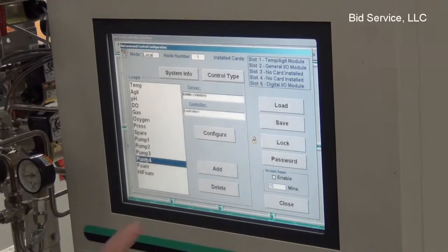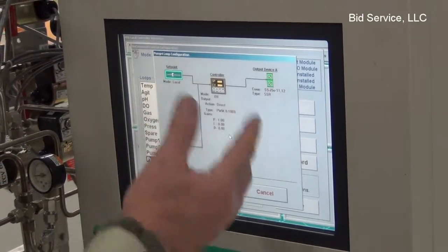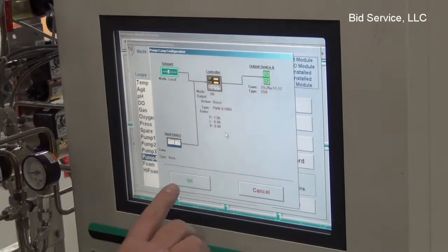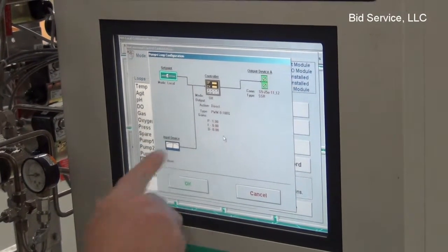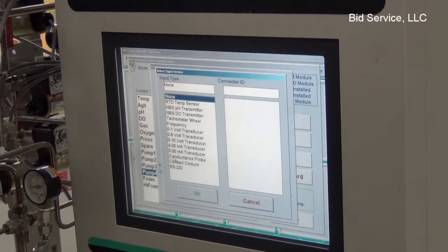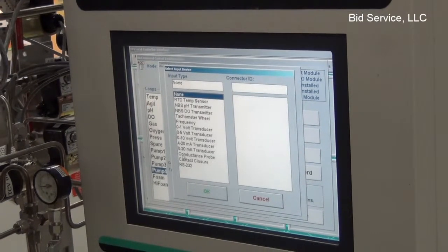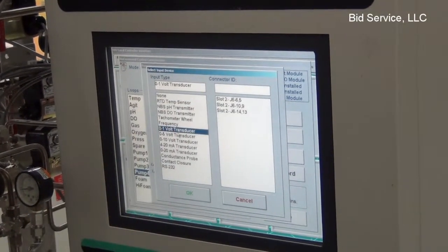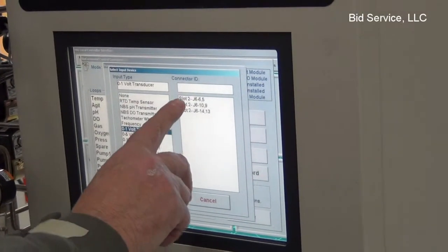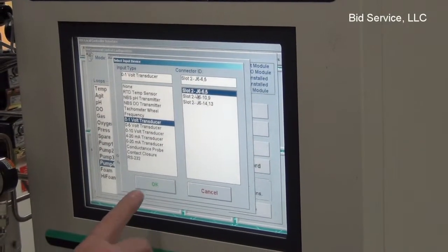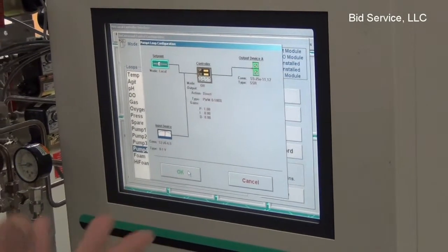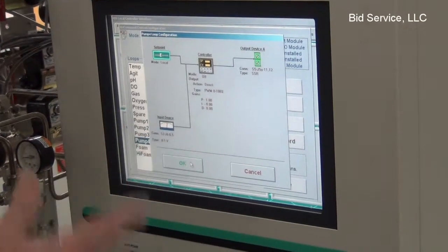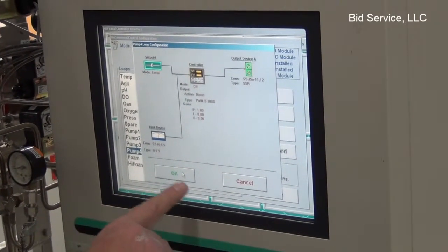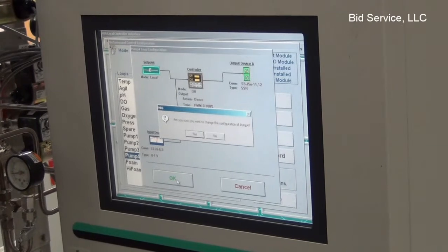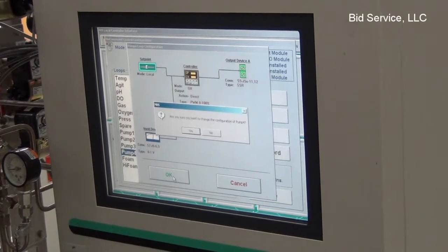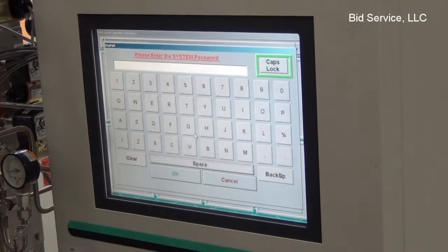So I would pick pump 4, say configuration. Again, it brings up this type of screen. I pick a device, so I'm going to pick the input device. Right now it's set to none. So I'm going to change that to a 0 to 1 volt transducer. I'm going to pick a slot, say OK. And it looks like it did it fine, it's there, but you have to actually OK it, so I'm going to hit OK. And it asks you, do you want to change the configuration of pump 4? And I want to say yes, so I hit yes.